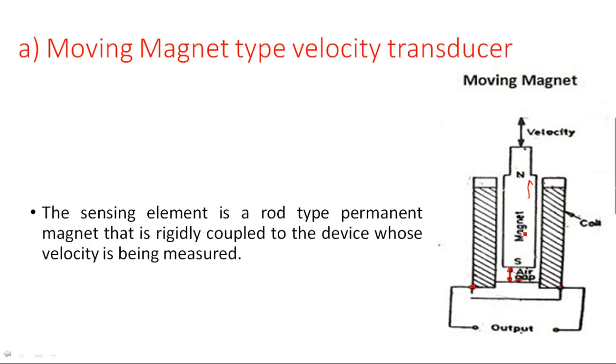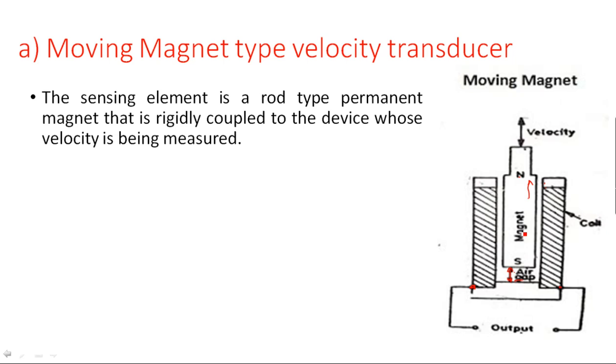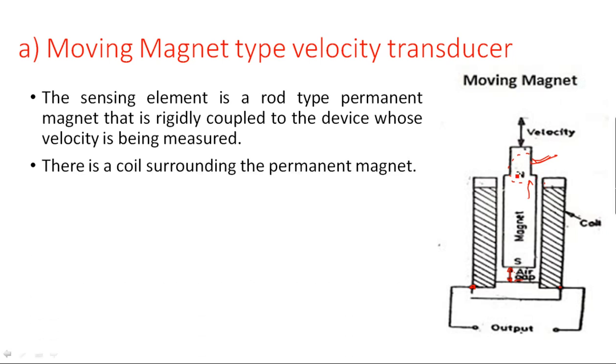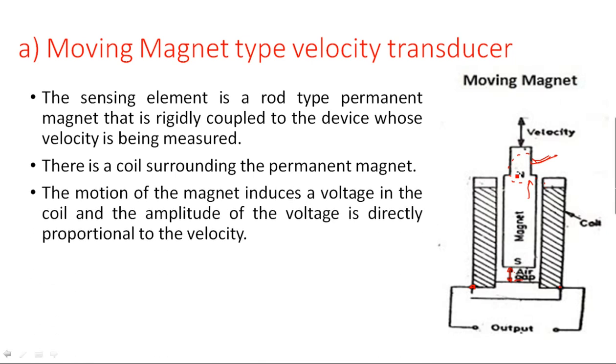The sensing element is a rod type of permanent magnet that is rigidly coupled to the device whose velocity is being measured. This rod type permanent magnet has north and south poles. When velocity is applied to the magnet, the resulting electrical voltage changes in the coil. There is a coil surrounding the permanent magnet, and the motion of the magnet induces a voltage in the coil. The amplitude of the voltage is directly proportional to velocity.